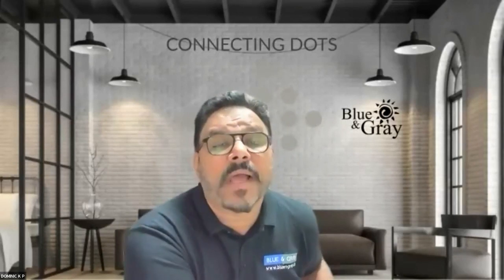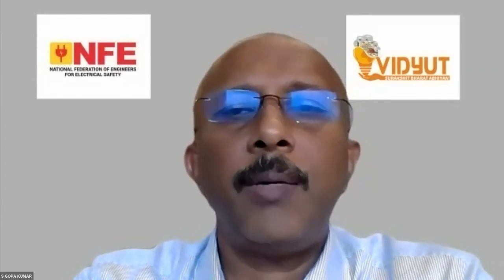Okay. Jatin Panchal is asking, as per NEC 2023, can you please highlight the use of fire survival cable for wiring the fire emergency in hospital? Does it talk about fire survival cable in NEC? Yes, fire survival cable is required for the emergency supply, not emergency, we call it safety service. Okay. So for the fire safety service, yes. Yeah. But please note that it is not only the fire survival cable, the entire electrical installation must withstand a certain time. That means the clip, clamp, conduit, supports, fixings, lights, junction boxes, and so on.